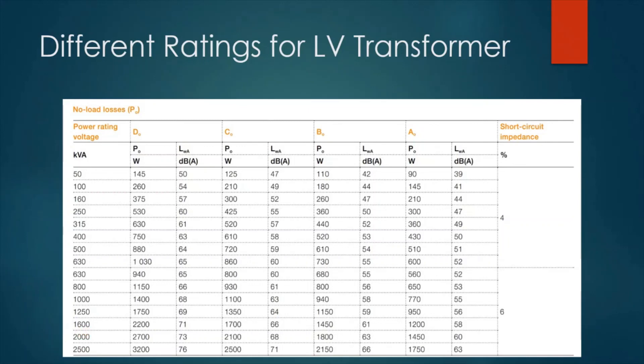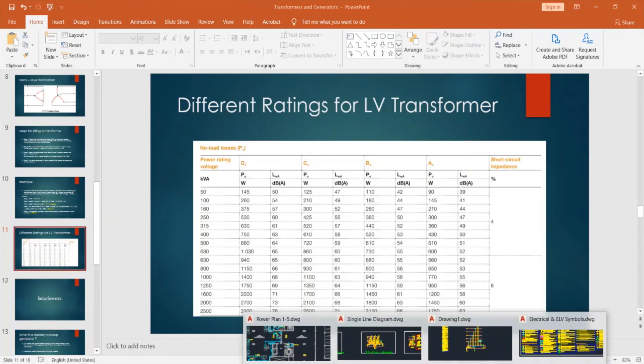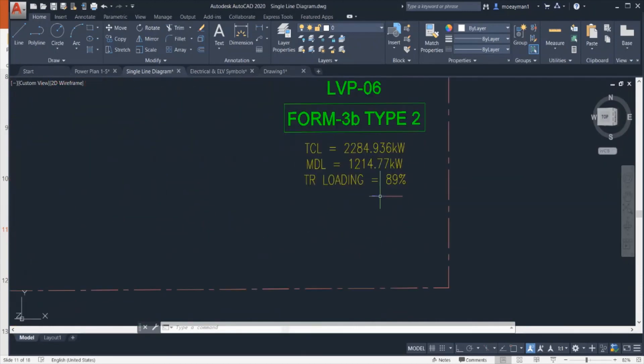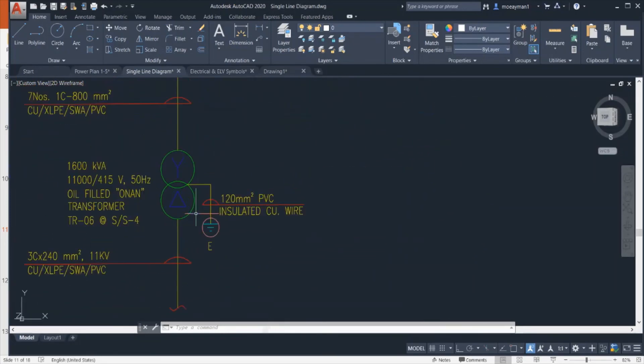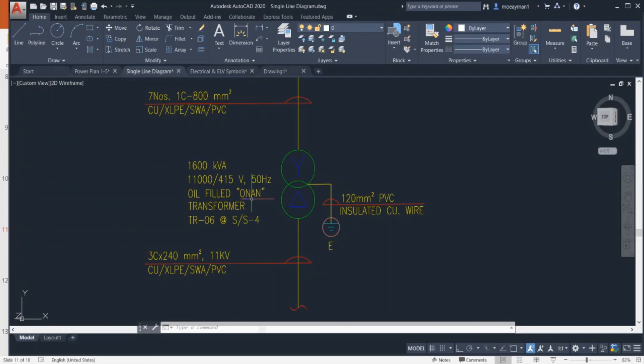Now let me show you how you will indicate the size and type of a transformer using a single line diagram. Opening the previously interpreted single line diagram, we check the demand load of this project, which is 1,214 kilowatts. Looking at the transformer, we find it is rated 1,600 kilovolt amperes, transforming 11 kilovolts to 415 volts. The type of this transformer is an oil transformer, specifically an oil natural air natural (ONAN) transformer. This was an explanation on sizing and selecting a suitable transformer for your project. By now, you should be able to size your transformer for any project easily.